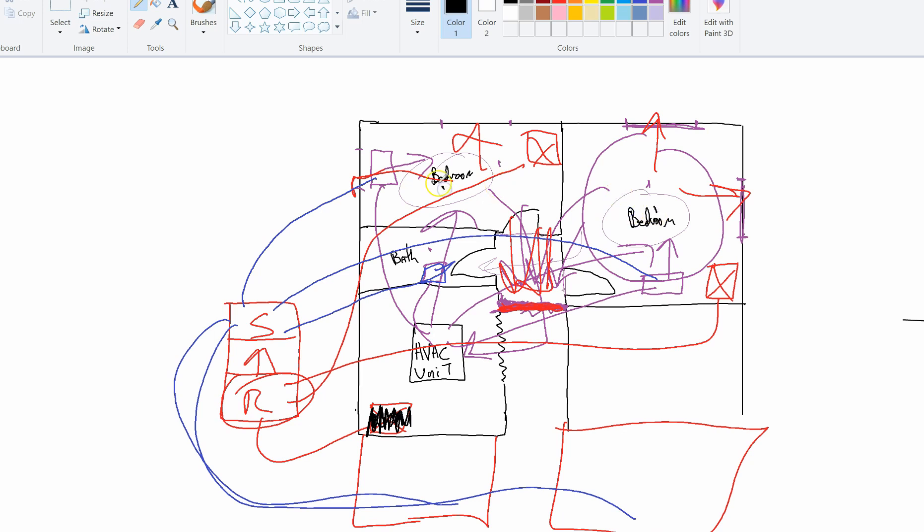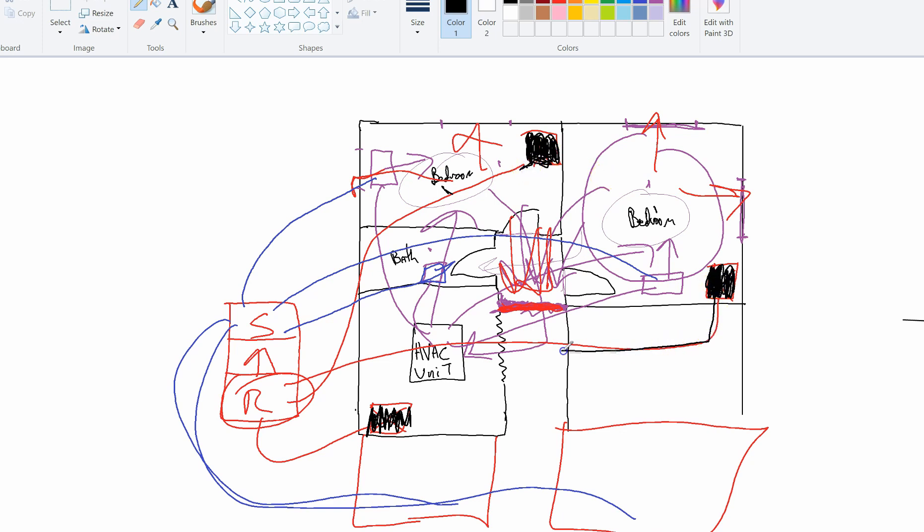Let's say we're isolating the two rooms that we use as the isolation rooms. We want to make sure we get good tape, whether it's duct tape or whatever, and you want to tape off these returns. You don't want to tape your supplies off. You still want to supply air into these rooms, but you want to block these returns. Why? Look what it's doing, guys. It's taking air back into the machine that could be contaminated air from this room and from this room.